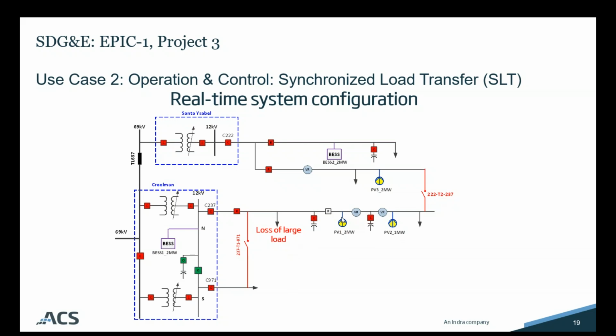will most likely cause an overinjection and possibly a reverse power event up onto the subtransmission level, which may not be desirable. So instead of just simply curtailing those large PVs, what can we do, since we're looking at this system as a full model? Can we use assets on an adjacent feeder to possibly divert some of that power injection and not just have to rely on curtailment? So with that, the model shows over injection. The model looks and it sees that we have this large battery storage device and it has available storage capacity.